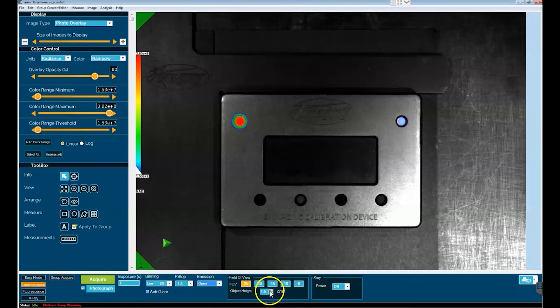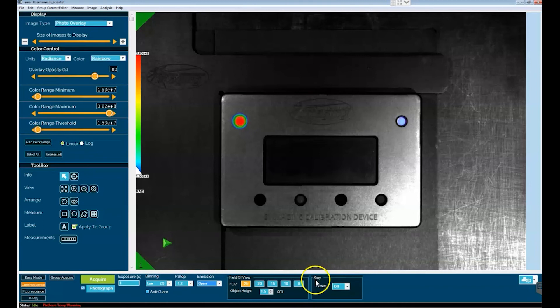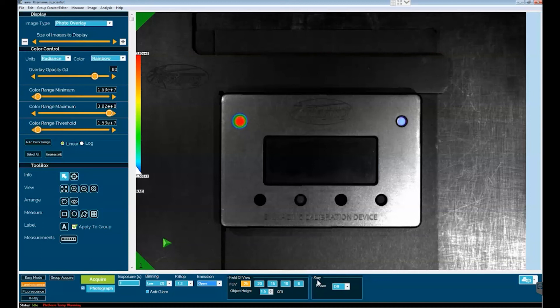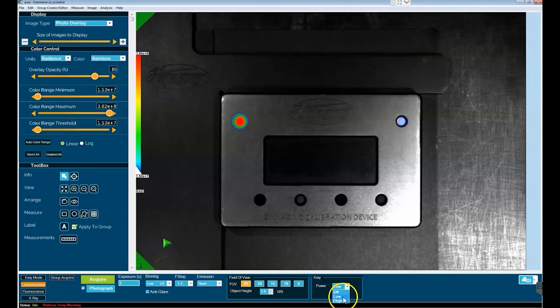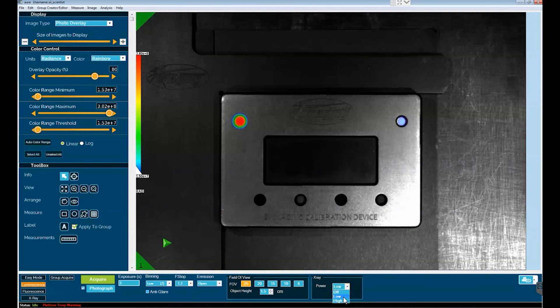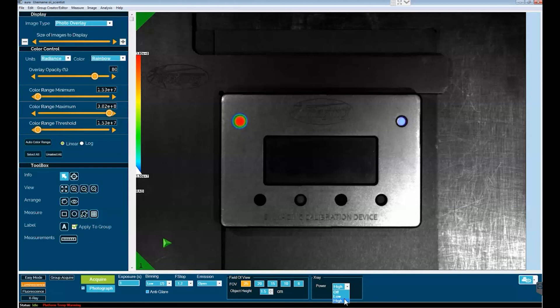The final parameter for bioluminescence camera settings is x-ray. Here x-ray is functioning as a background or atlas modality in Aura - you will be able to co-register the optical data with the x-ray image and so determine exactly where the optical data is arising from in your target. You have two different energy levels, low and high, that you can select from. Lower energy x-ray at 10 keV will be used for low density smaller objects such as insects or neonate mice. High energy x-ray at 40 keV in the Ami HTX and 50 keV in the Lago X are typically used for imaging adult mice and rats.